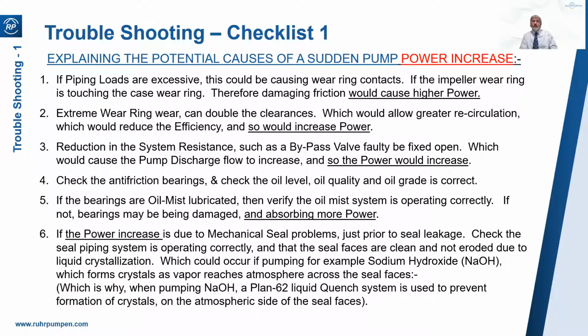Possibly there could be mechanical seal problems. They might not be leaking yet, but you've got potential problems. So check your seal piping system and the flush is working correctly. Check if you've got a plan 62, a quench on the outboard seal, particularly if you're handling something that crystallizes like sodium hydroxide. When sodium hydroxide migrates through the mechanical seal, if it meets the air, it will crystallize and could tear the faces. Similarly, a hot oil pump.